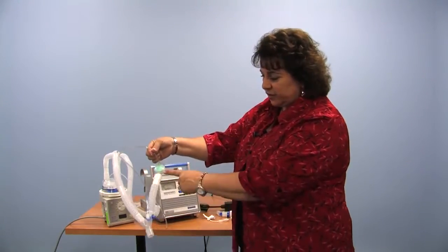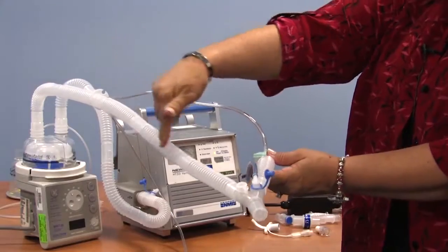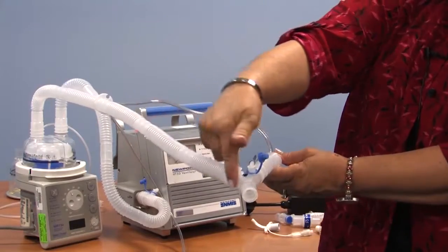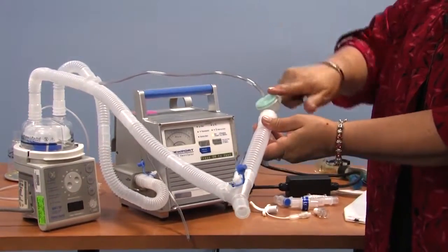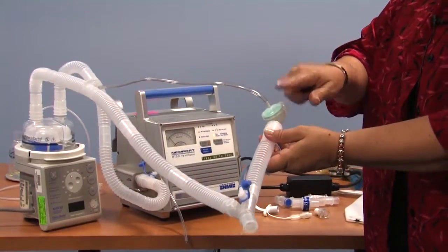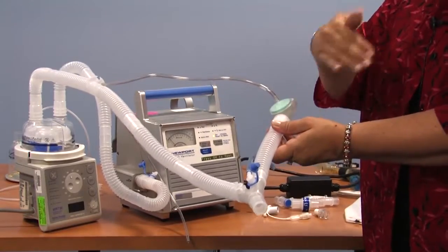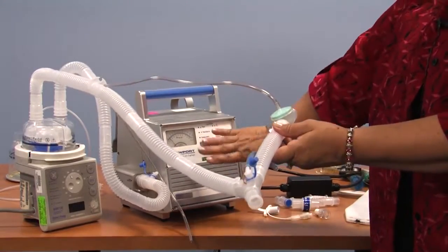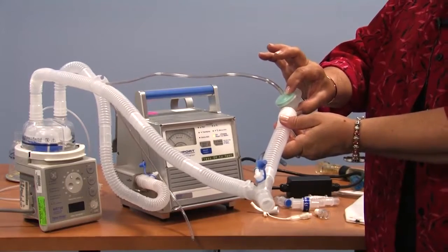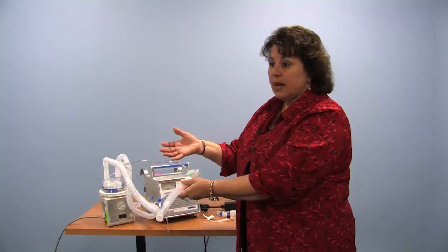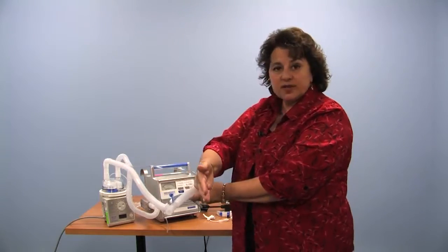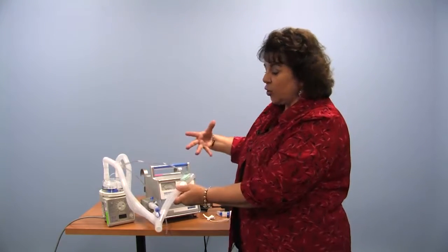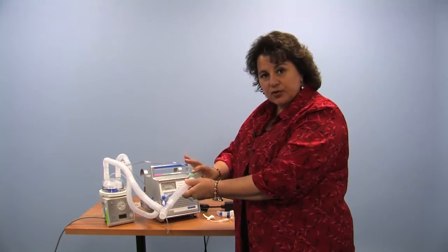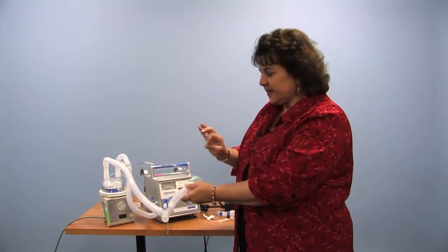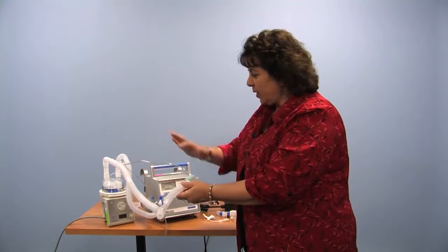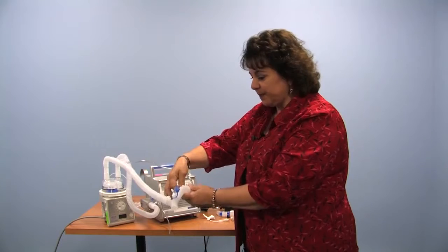This is the exhalation valve we mentioned, so the patient breathes. The gas comes here into the patient and goes here out through the exhalation valve. This controls the pressures, the volumes, the PEEP, the time. So the settings on the machine, this is where the machine gives input for what the machine should do. I should close and fill the lungs for 1 second, and then I should release and open. I should hold a little bit of pressure there because you told me you wanted 6 centimeters of PEEP. So it's important to have everything connected here.